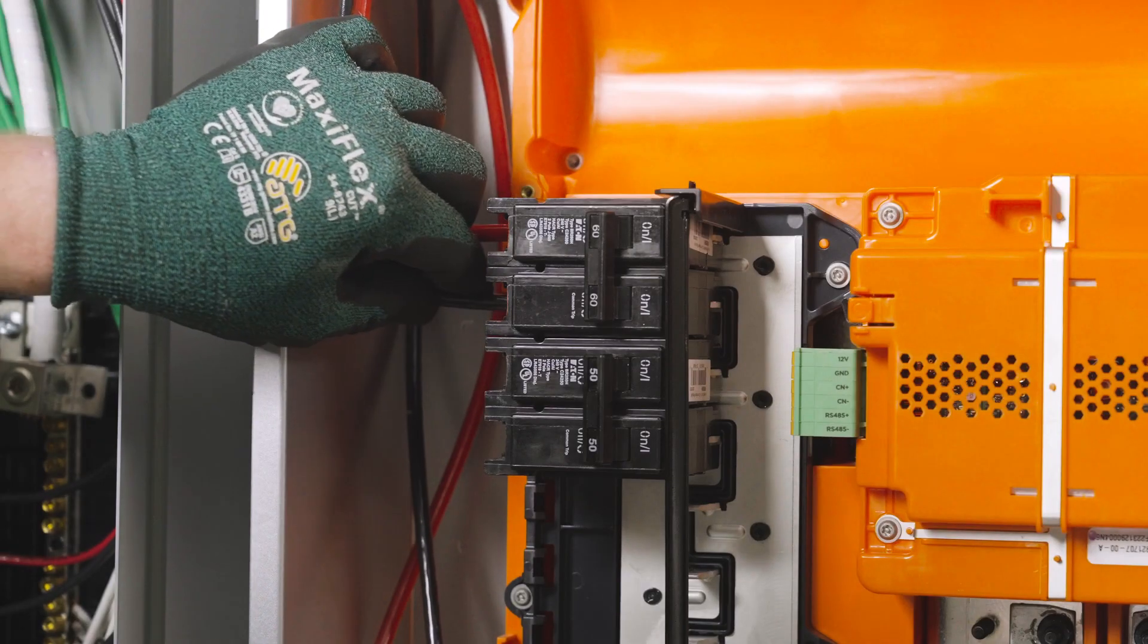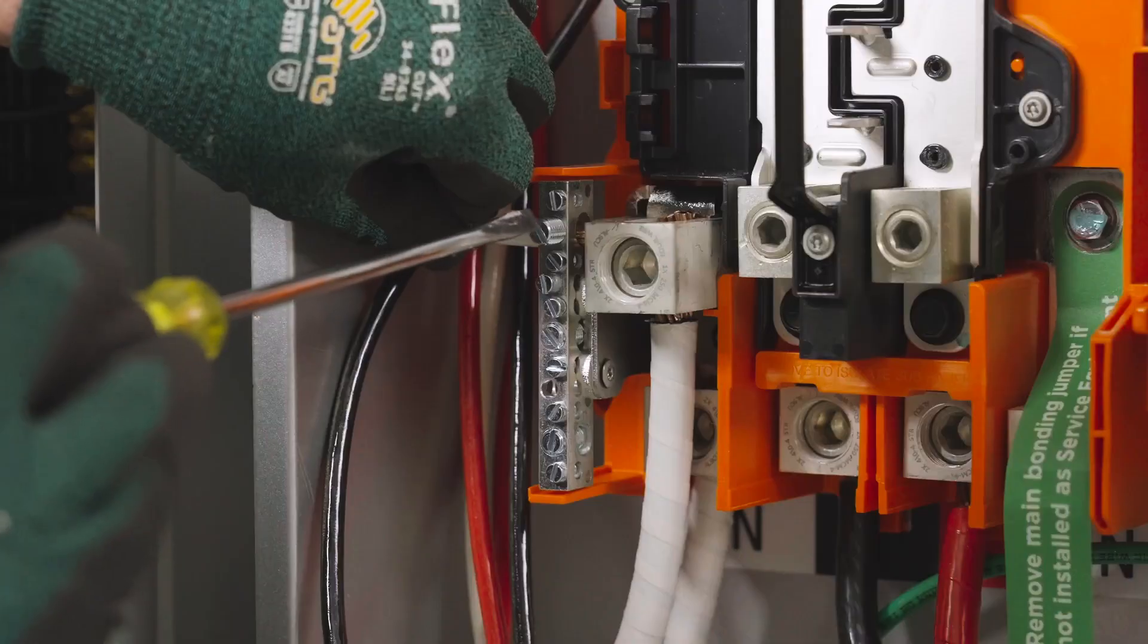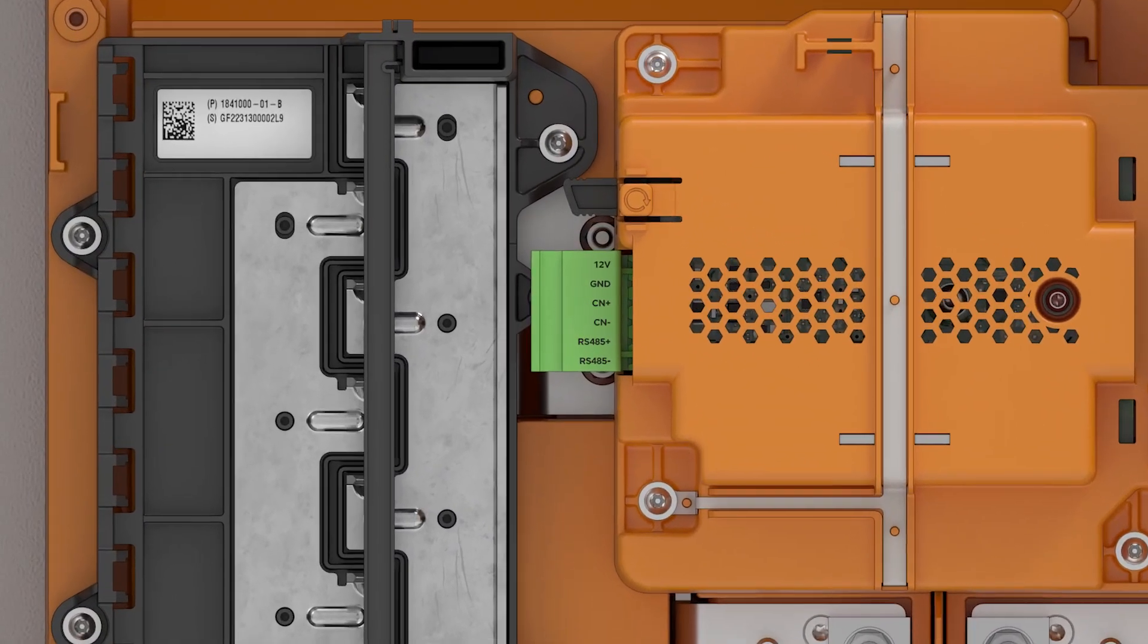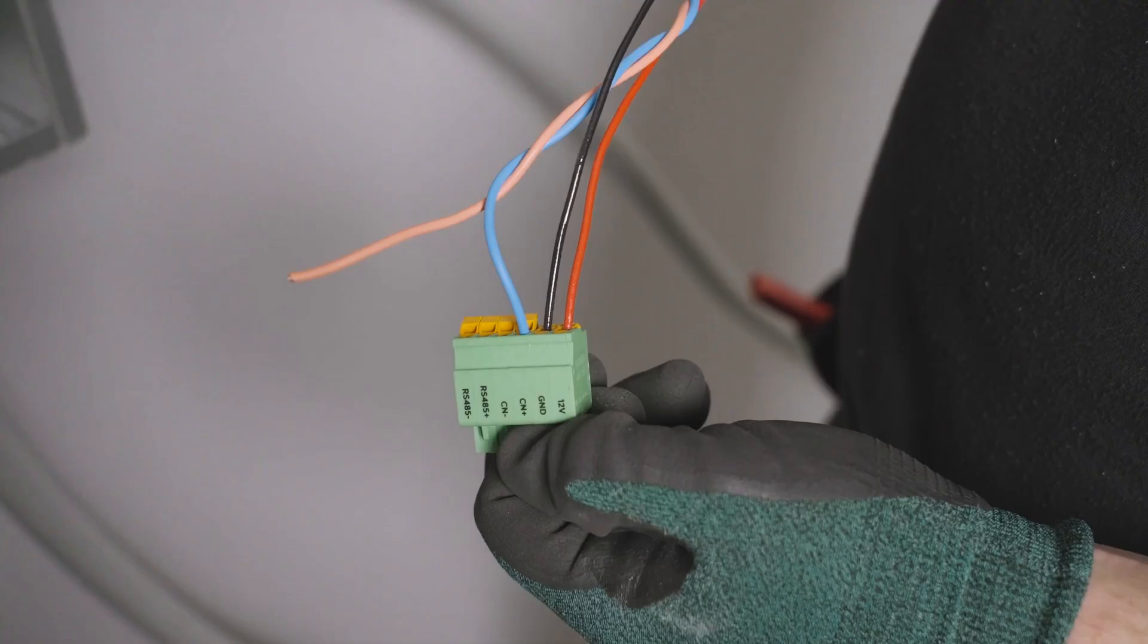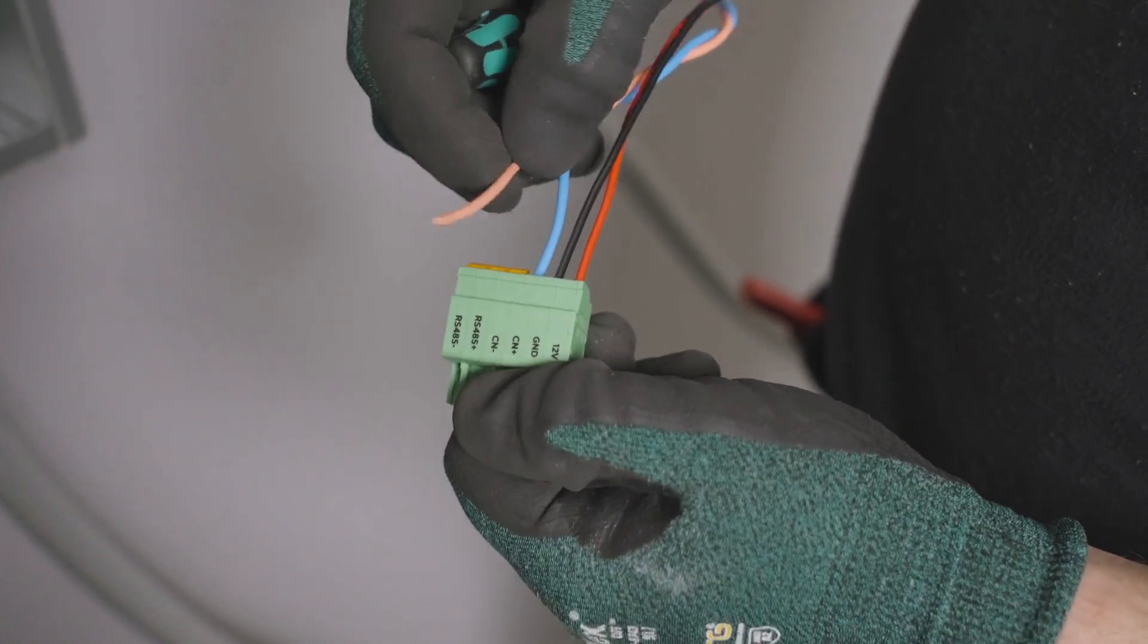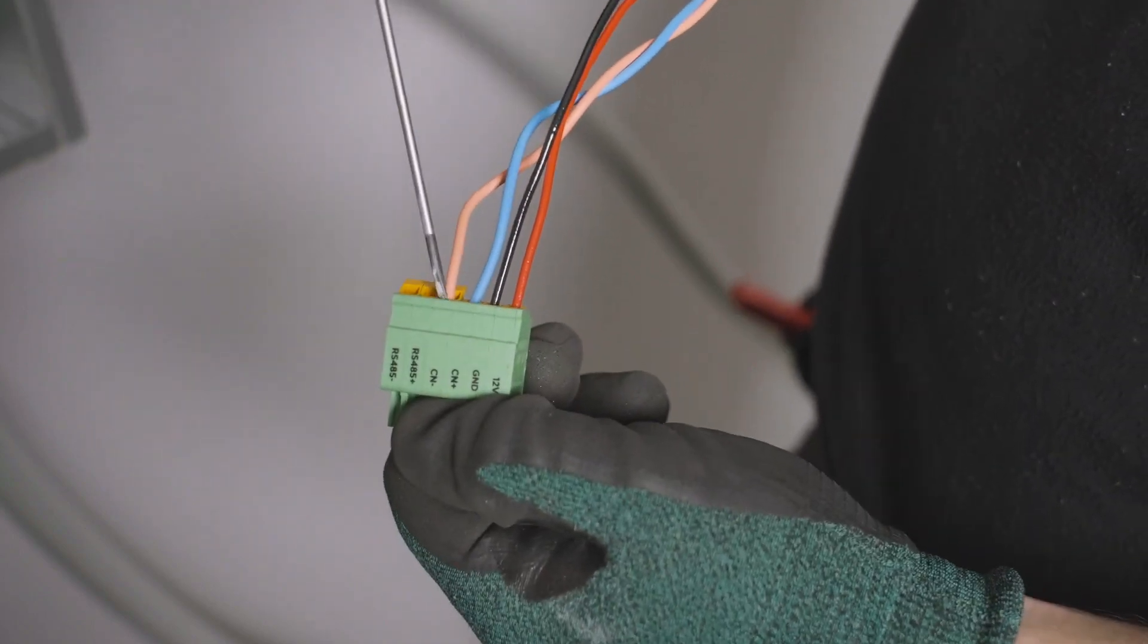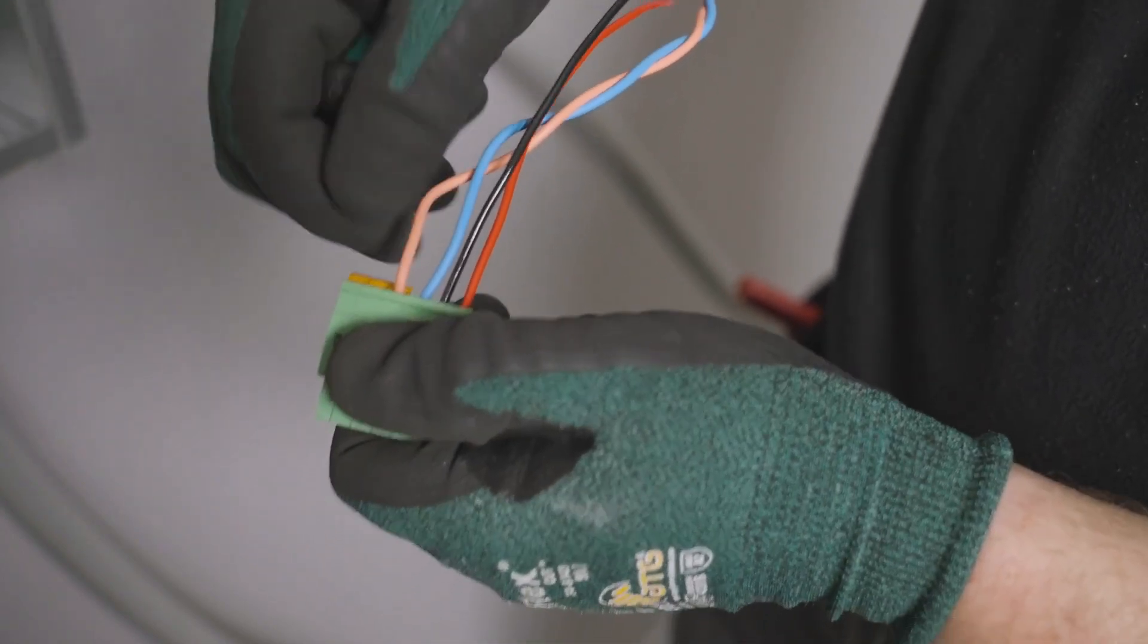Back in Gateway 3, terminate the branch circuit wiring for Powerwall on the breaker, neutral bar, and ground bar. The communication cable is terminated in here. Remove this connector to make the terminations. Lift the orange tabs on the corresponding ports and insert the unstripped communication wiring into the connector. Use a small screwdriver to close each port that pierces through the insulation of the communication wires.